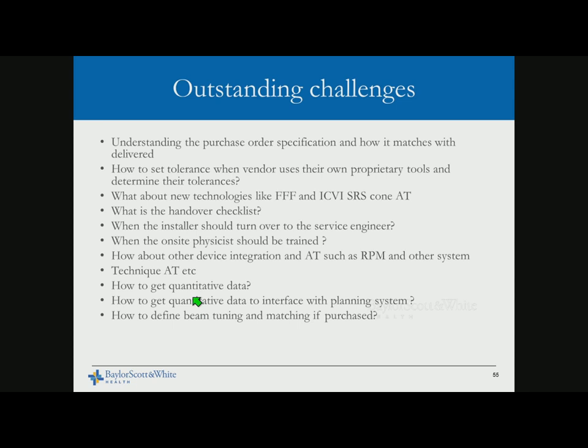Beam tuning and beam matching, if purchased, are also challenges. Customers have complained that beam matching is not done properly due to different flattening filters — vendors sell a beam matching program but cannot achieve the match with their own criteria or the planning system, leaving the customer without resolution. Administrators often get involved in these discussions, leading to miscommunication between vendors and administrators and frustration at acceptance testing. These things need to be clearly stated in the contractual document.